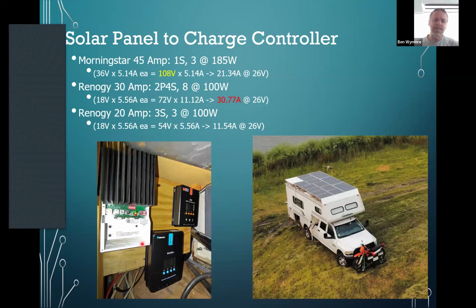But it turns out it is a big deal, because the voltage curve of lithium iron phosphate batteries is very flat. The state of charge - how much battery you've got - at 60% on a 24 volt system might be 26.6 volts, and at 90% it's 26.8 volts. So the difference between 60% and 90% charge is only 0.2 of a volt. When you're pushing a lot of current, the battery's actually at 26.6, but the solar controllers detect it as 26.8 because of that resistance - you're trying to shove milkshake through a coffee stirrer. So the controllers think the battery's full, and they stop.